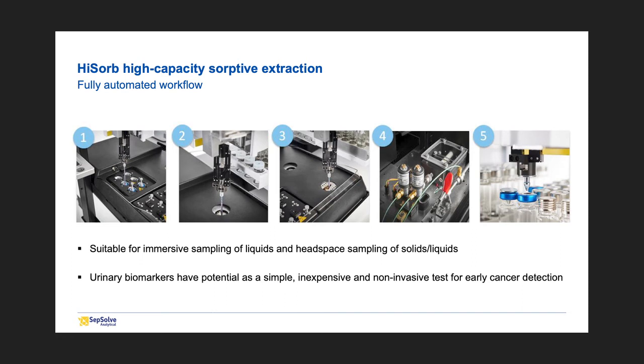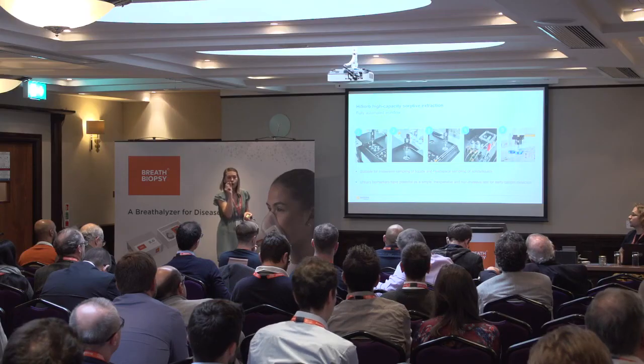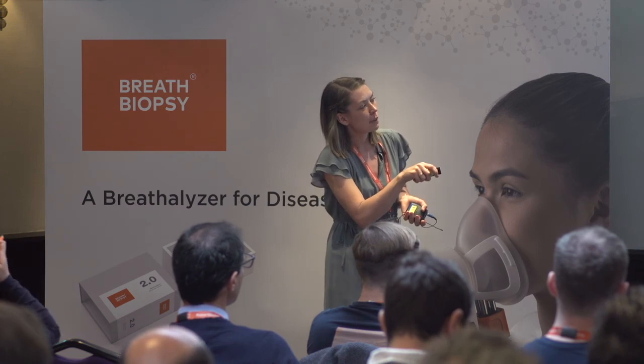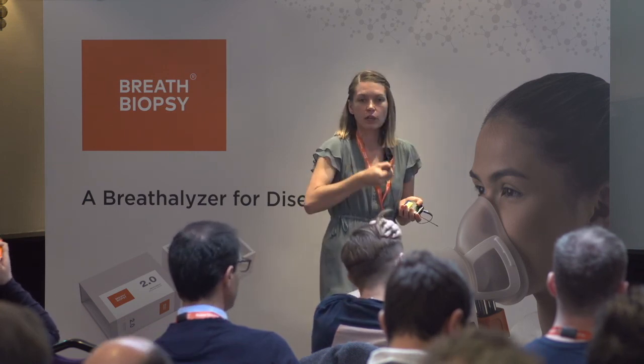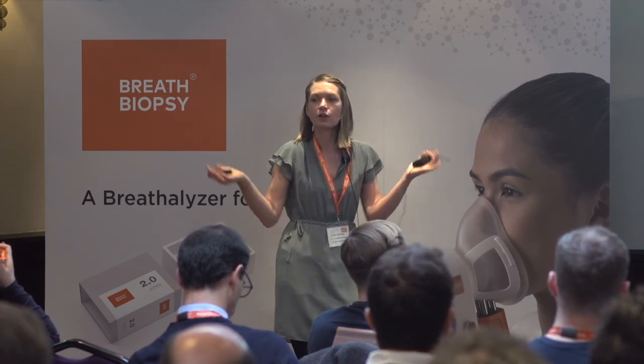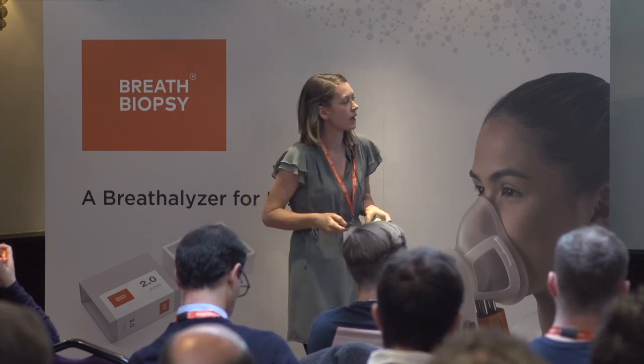It then takes the probe to a wash station where it will rinse it free of any matrix and dry the probe. Then it will desorb the probe in the inlet. The analytes are sent to the trap for analysis by GCMS. And since they are wider than your average SPME fiber needle, we do have this capping tool here, which can plug the vials to ensure that none of your sample is lost to the lab air or nothing from the lab gets into the sample.